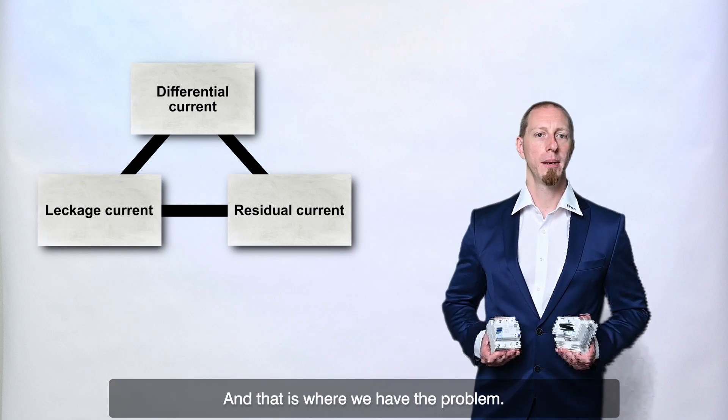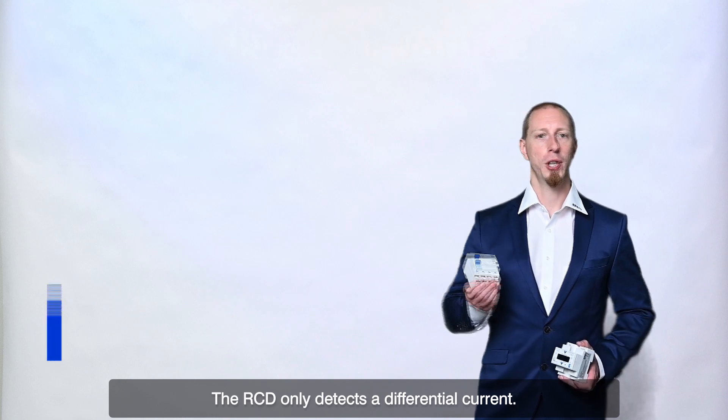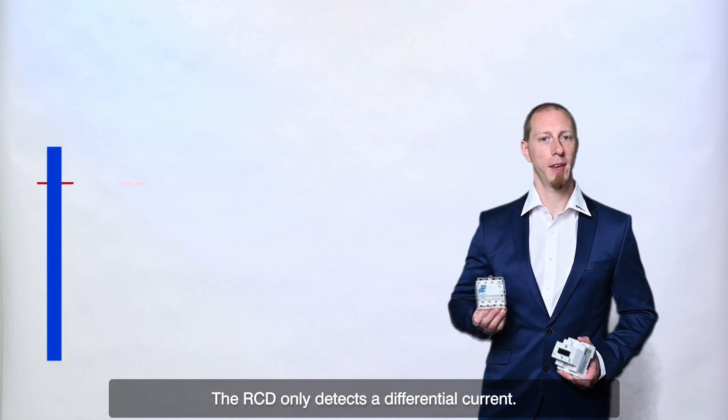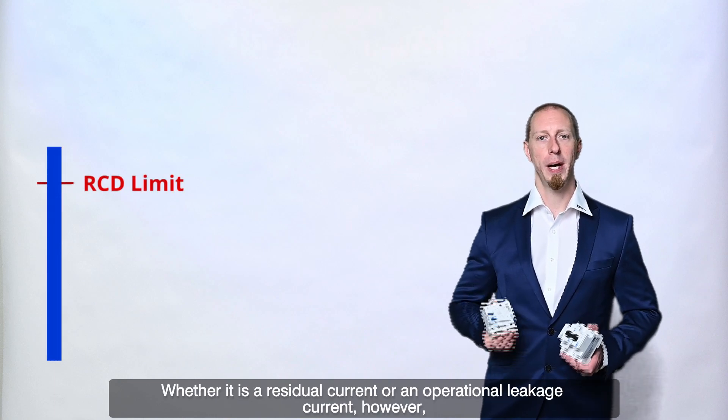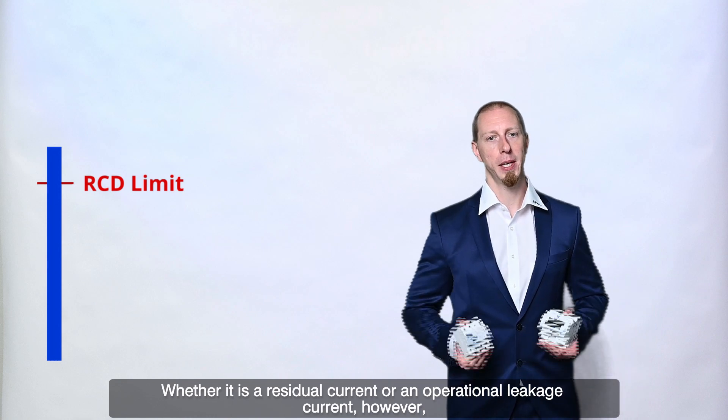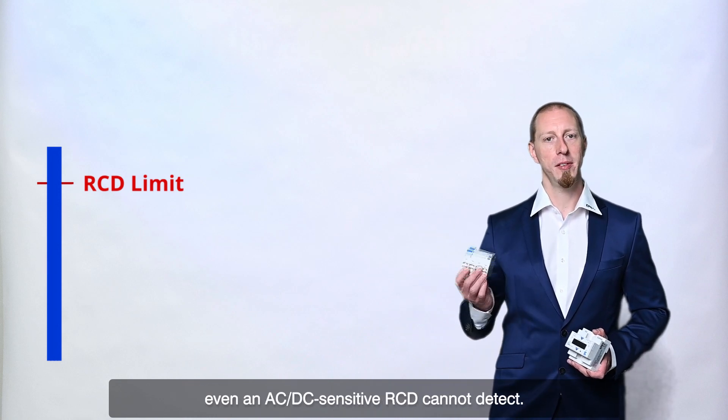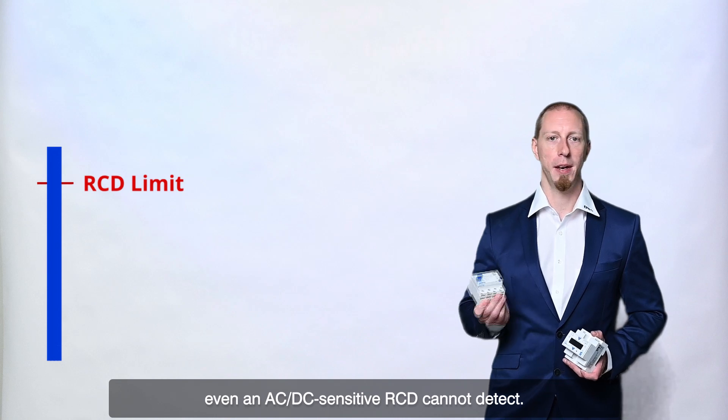And this is where we have the problem. The RCD only detects a differential current. Whether it is a residual current or an operational leakage current, however, even an AC-DC sensitive RCD cannot detect.